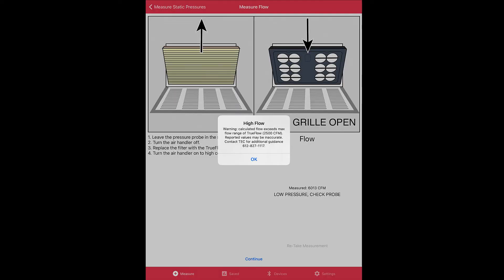You can see on the screen that we've got a notification for a high flow limit, so we will not be able to capture this measurement because we exceed the plate's available measurement capability of 2500 CFM. Now if you get below 300 CFM you will get the same warning. This is the high flow and low flow limit notification.